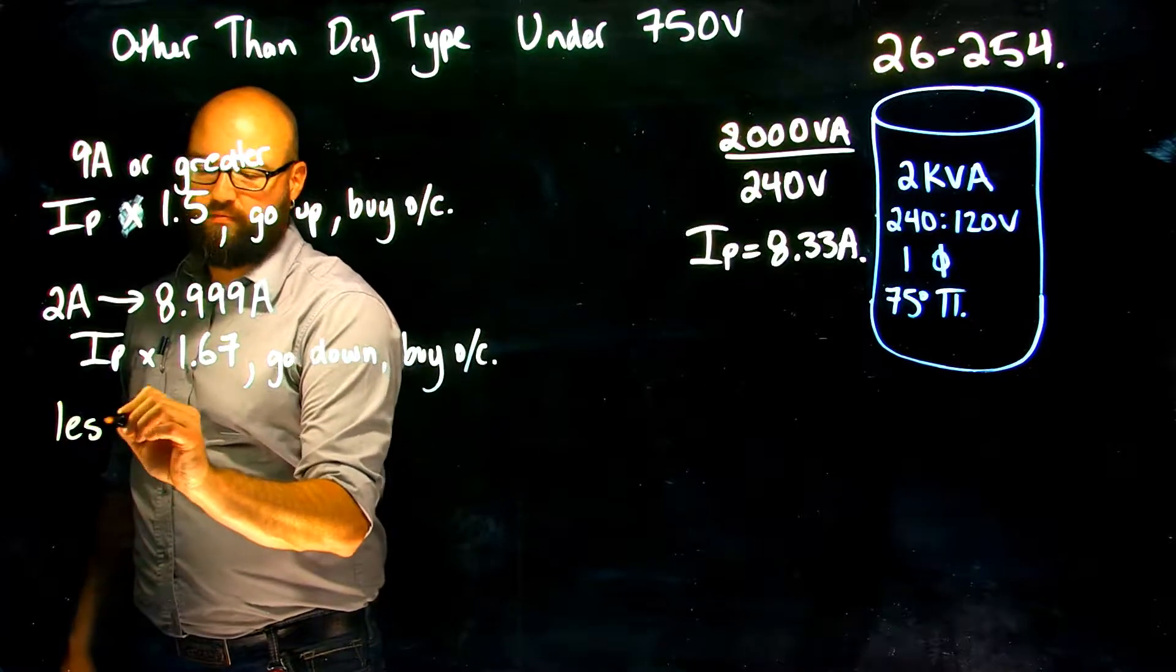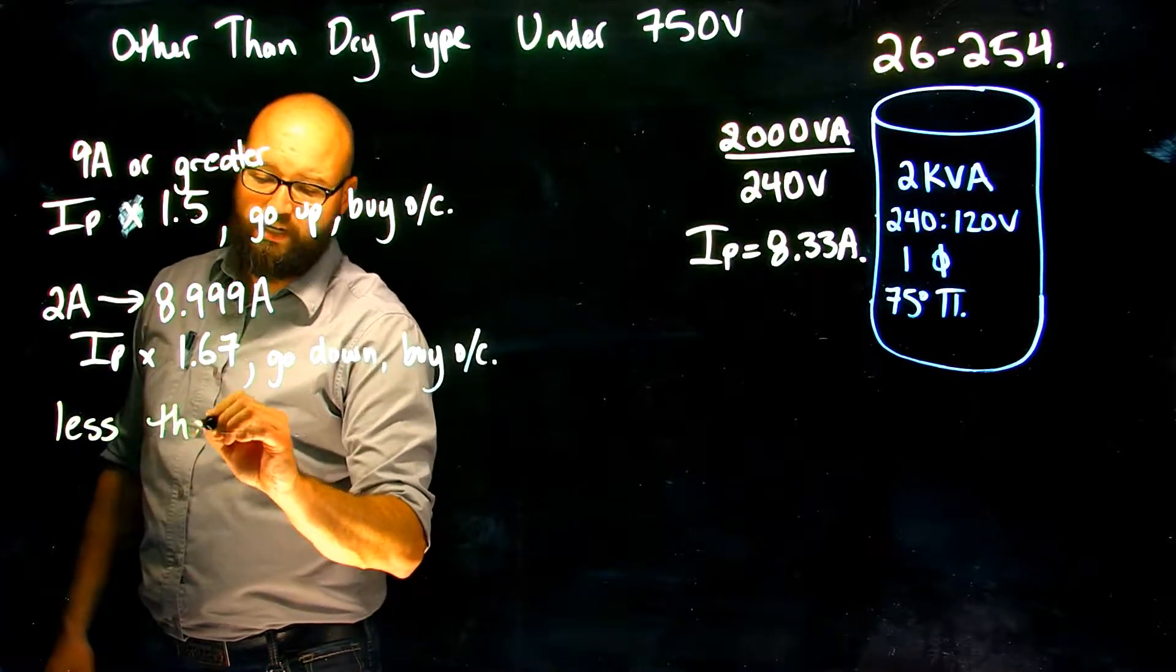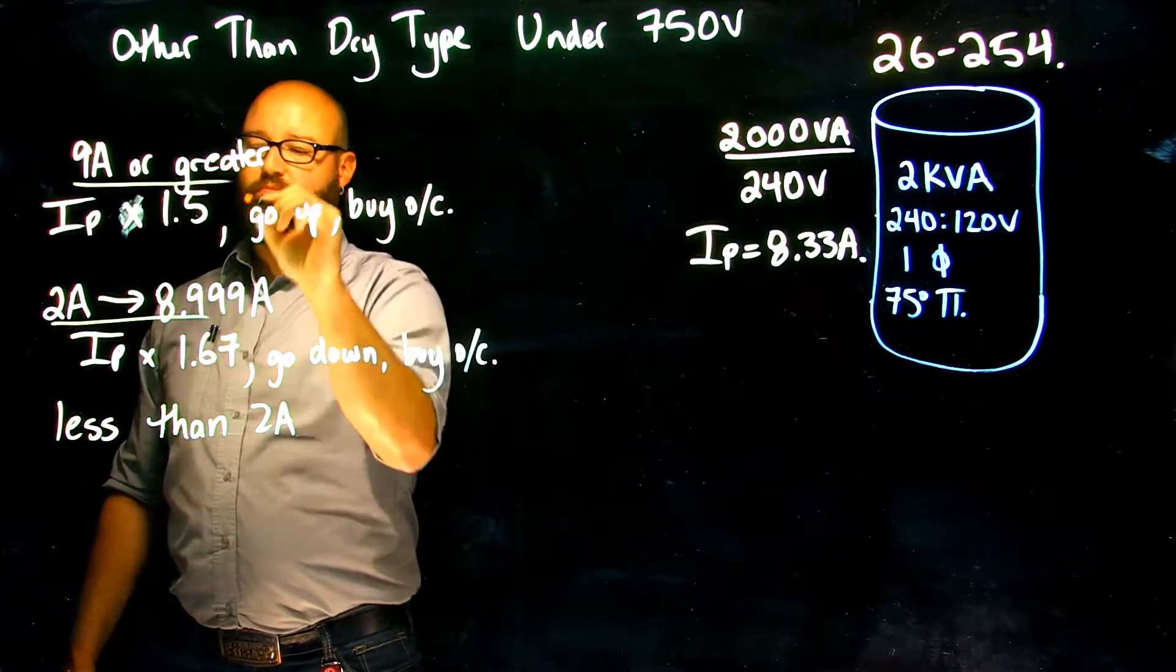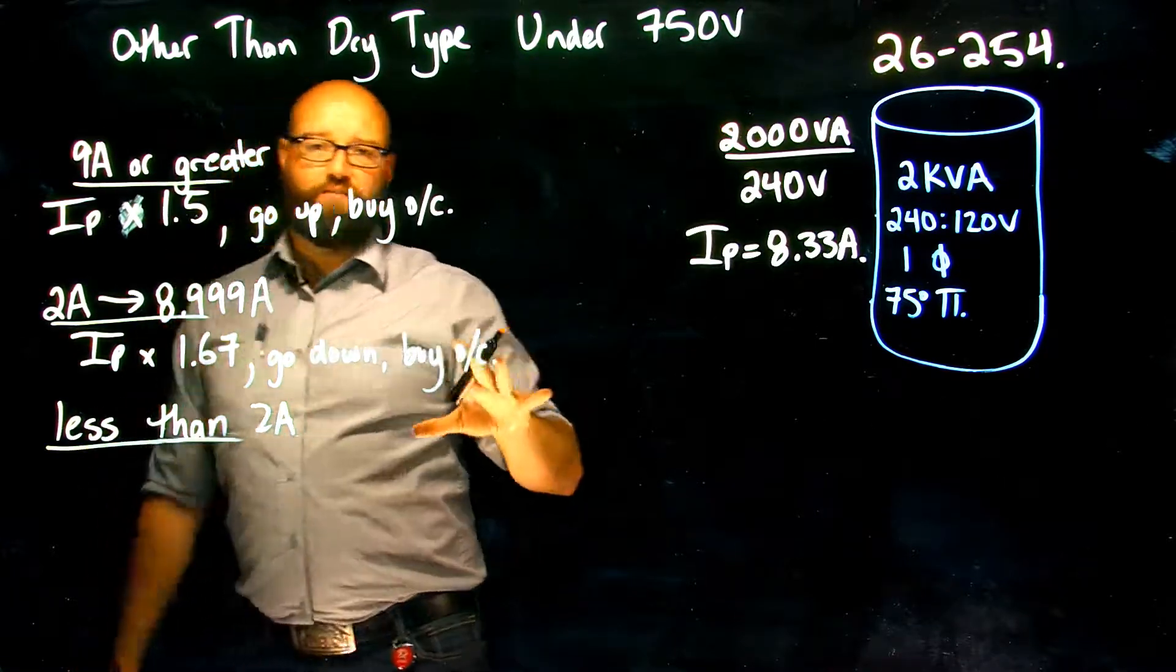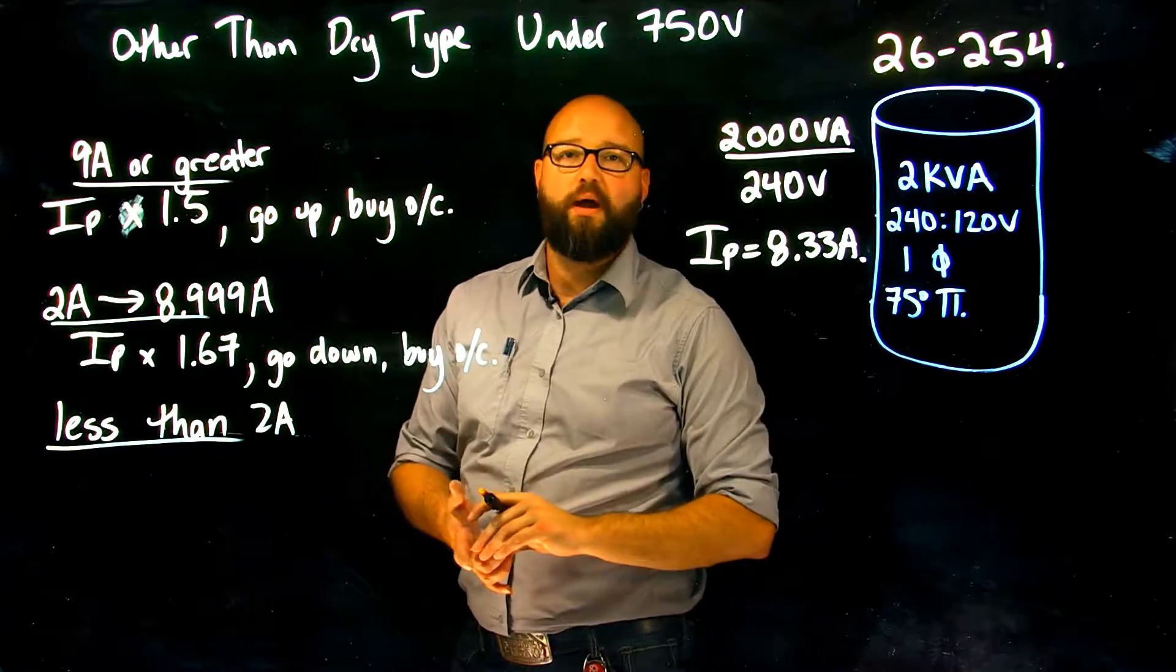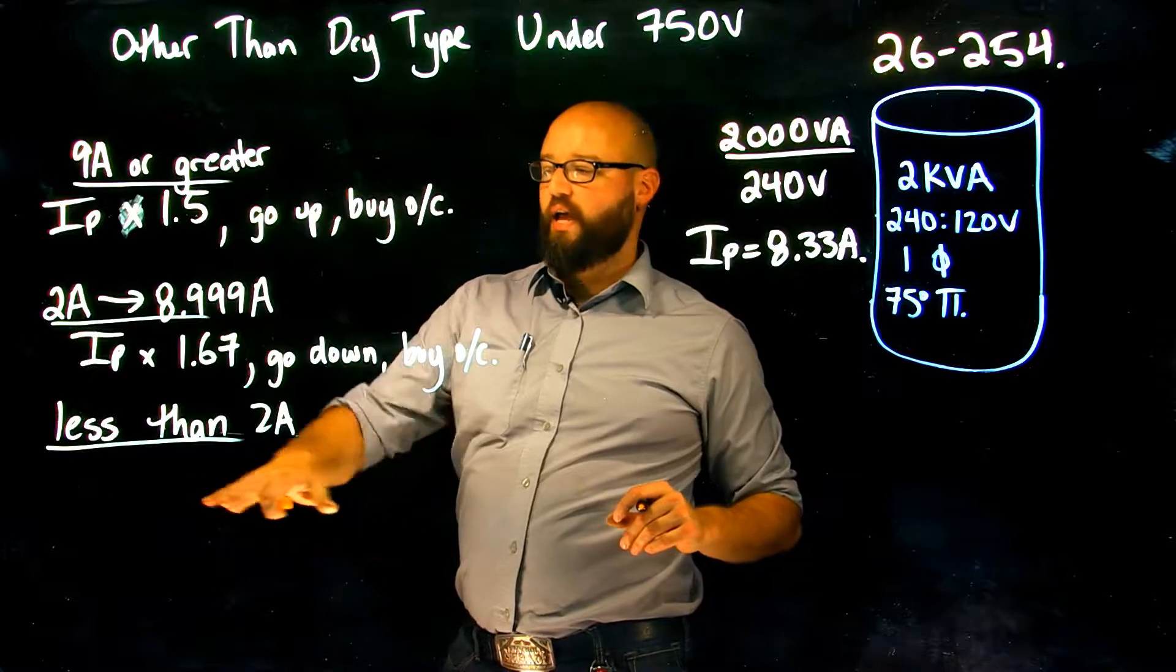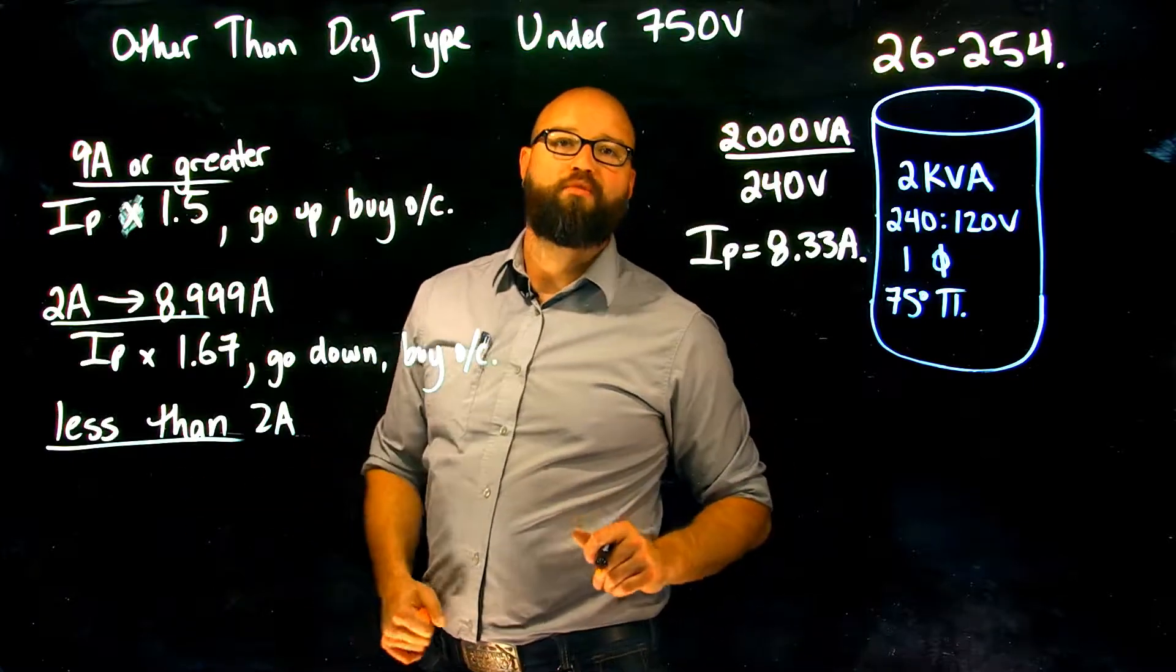Finally, if it's less than 2 amps, if my rated primary is less than 2 amps, if I read on it tells me I am going to use 300 percent as my multiplier. I cannot have an overcurrent rated or set at more than 300 percent of that rated primary current.